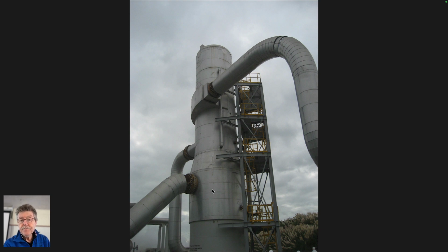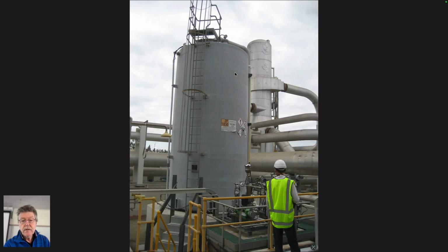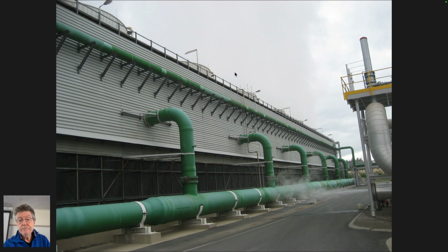I guess this is a water steam separator. Water comes in at the bottom. It's turned around. The water flashes to steam. The steam vaporizes and is taken off the top, and the water is removed. So perhaps this is the inlet, perhaps this is the outlet for water, and perhaps this is the outlet for steam, which makes sense. I think this is acidification to be able to make sure you keep the reservoir and the turbines from not dropping silica and plugging up.